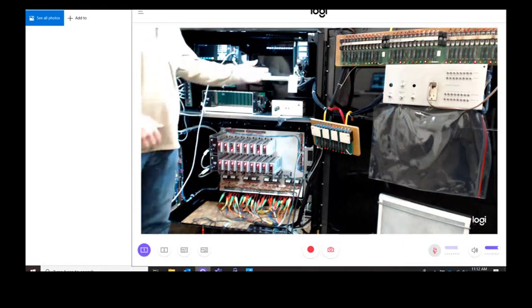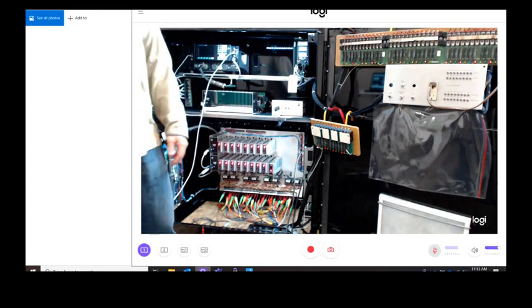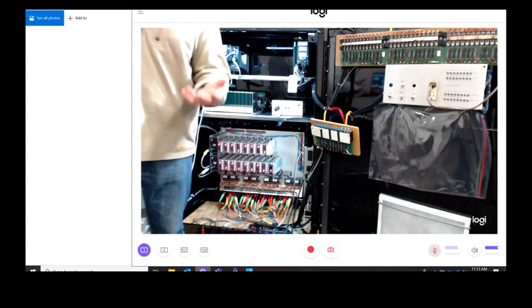So basically, a port 1 fail with the MMU, it's either going to be the cable or it's going to be the MMU itself. So that's pretty straightforward. Again, it's key to have spare parts to do this.